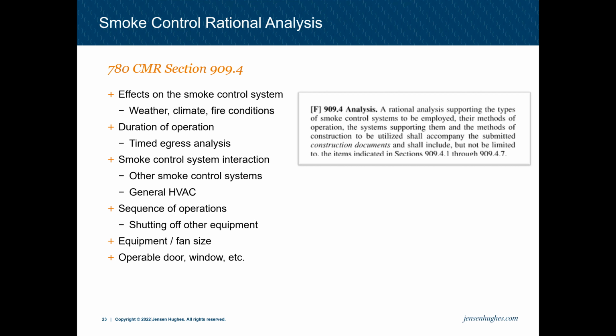Also, for atrium exhaust systems, you do have to do a timed egress analysis. And that's verifying how long people take to evacuate or egress from the space of concern. The rational analyses should go over smoke control system interaction, which includes the interaction with other smoke control systems and the general HVAC. Along those lines, there should be a sequence of operations.